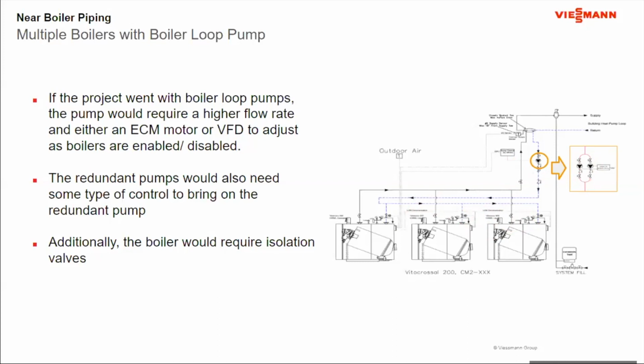Okay. And from a design standpoint, I do this, and then I can set the flow through the boilers based on the needs of the load on the secondary side. A lot of times this is looked upon favorably, and some will say they like the idea of doing this because they're thinking of a single pump and isolation valves versus putting 3 pumps, 1 on each individual boiler. The thing to remember is when I do this, from an aspect of redundancy, it's not a single pump. It does have to be 2 pumps. And it's recommended that those 2 pumps are also running off of VFDs or ECM motors. And with the 2 pumps, I also have to have a control that will rotate between the 2 pumps as needed for loading of the system.